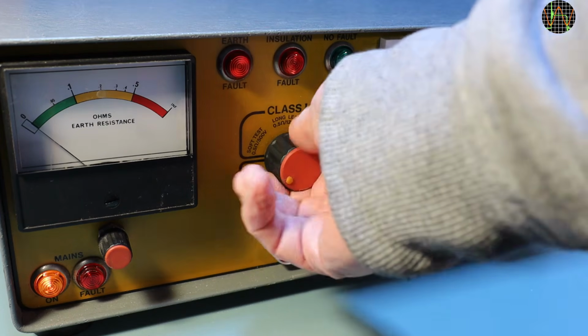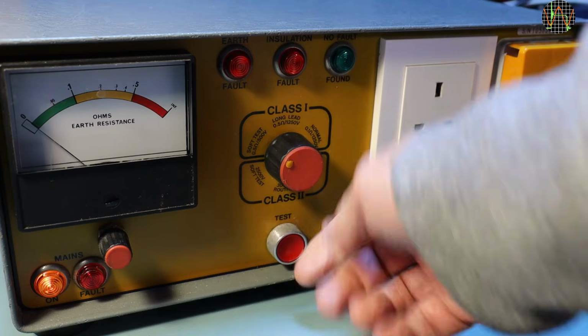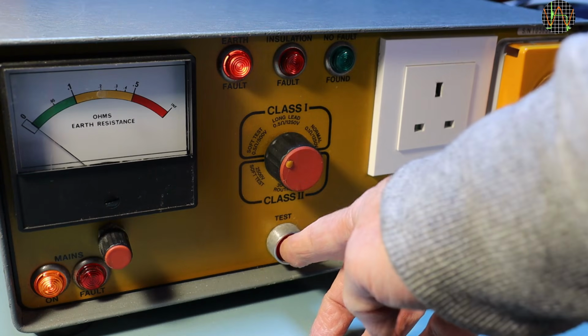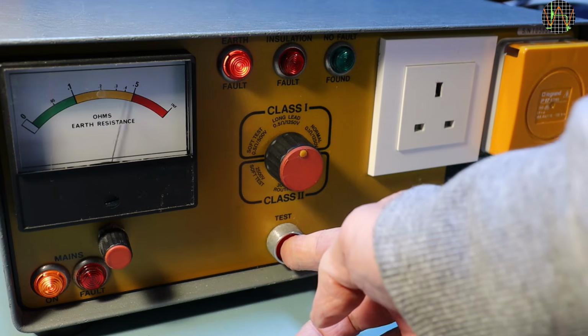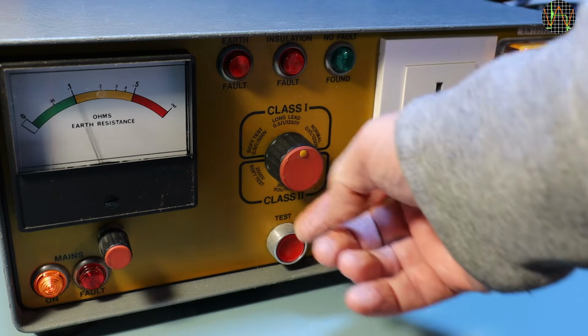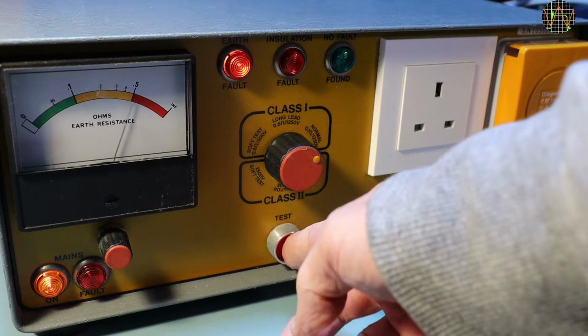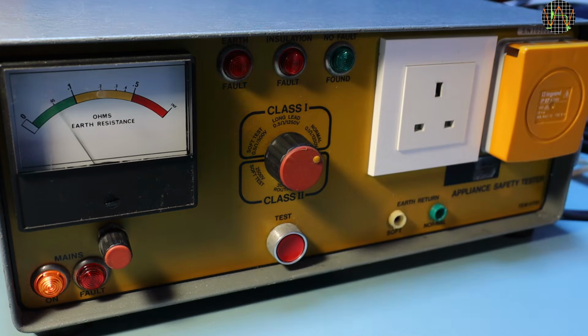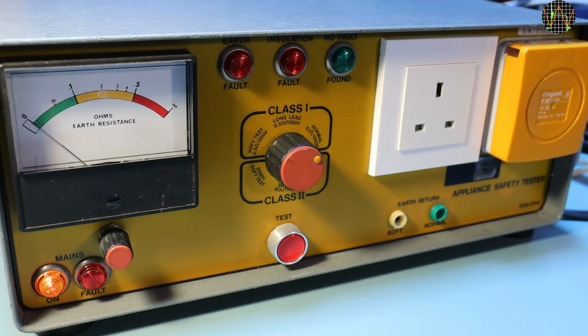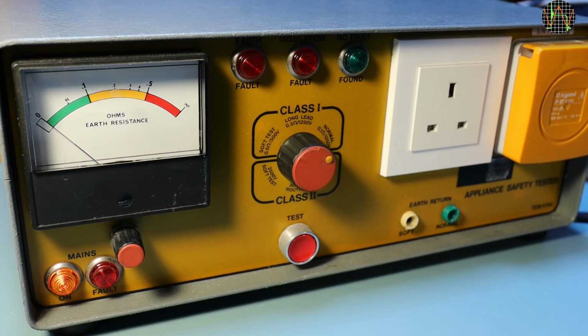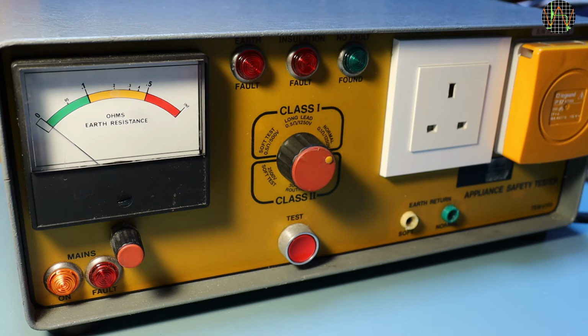In a similar way, I expect all the tests for class 1 to fail with an earth fault, as the unit cannot find an earth connection. The meter is deep in the red zone, but not quite at infinity as it should be, so that will need to be adjusted, but so far the tester seems to work as it should. As I mentioned, with nothing connected, the class 1 test should show an infinite earth resistance. It isn't at the moment, but that is easy to correct.